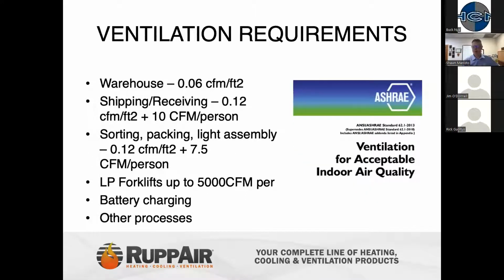So one big thing is the ventilation requirements. It's important to point out that even an empty box does need some level of ventilation. As far as ASHRAE references in the IMC codes, they will reference a warehouse as having a minimum of 0.06 CFM per square foot. In some cases, people will take exception to that when it's an unoccupied spec building, but as you will see as we go through this presentation today, some level of ventilation is still critical for keeping these buildings dry and clean and ready for tenant finish out when that day comes.